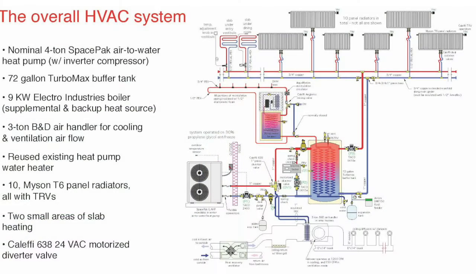First stage controls the heat pump. Second stage controls an electric boiler right here. This is an Electro Industries boiler, 9 kW. I'll show you a picture of it. It just mounts on the wall. And if that's needed, it kicks in on the second stage.